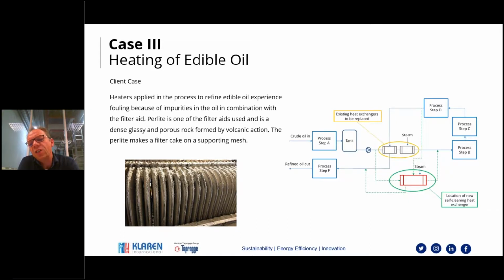So in the first heat exchanger, we recover heat from another oil source, which is a hot source, having a temperature of around 130, 140 degrees. And we recover the heat from that, and in parallel heat the primary oil that goes to process step B. This heater is followed by a second heater which is driven by steam, and what they see in the actual application is that over time they need more and more steam to compensate for the fouling which they have in the first heat exchanger, while at the same time the second heat exchanger is also fouling. So at the end, they cannot reach the desired temperatures, and they don't recover as much heat as possible, meaning that there's really a business driver to look for an alternative.